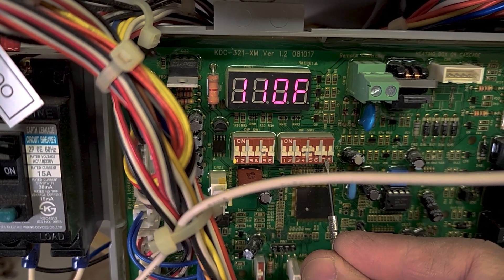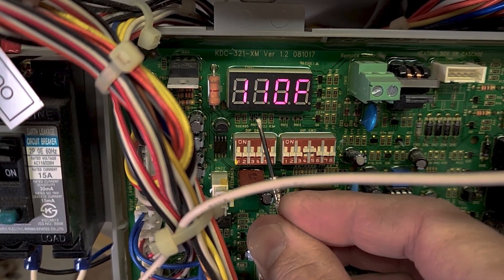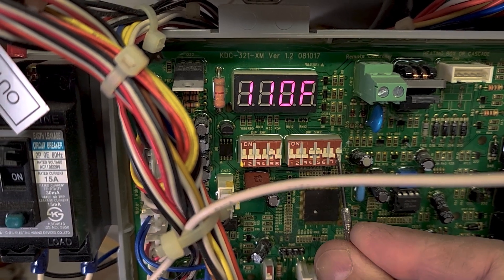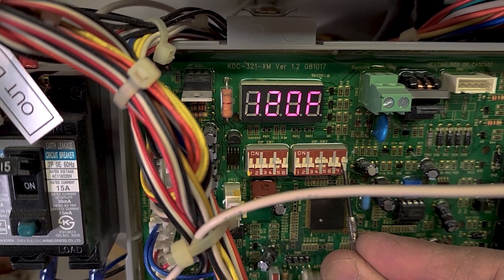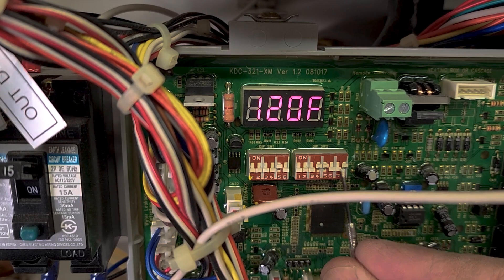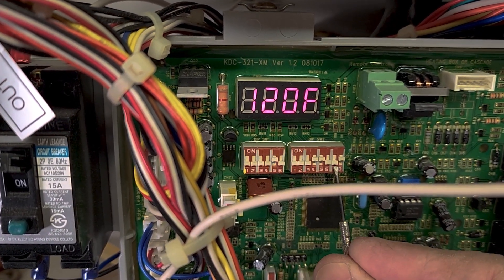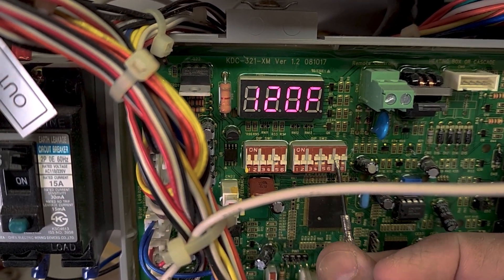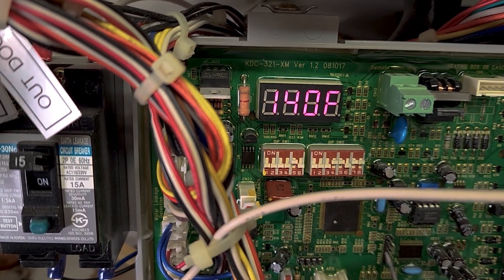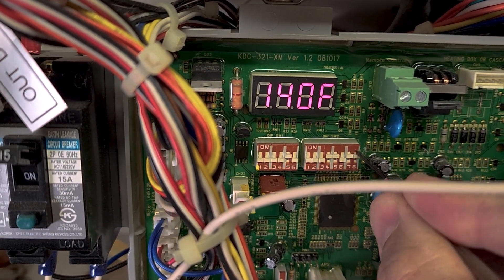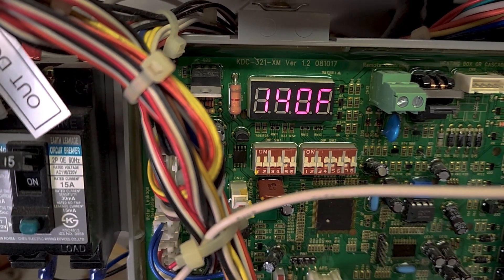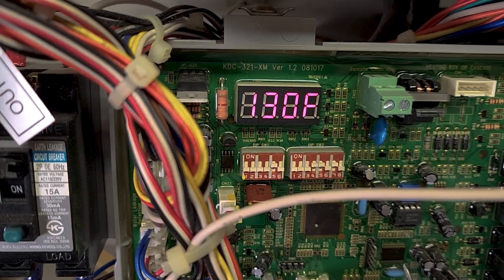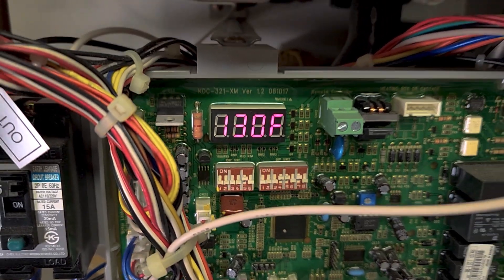So with both seven and eight being down, it will be 110 degrees. If you flip eight up, it'll move to 120. You can see that on the digital readout now. If you move this one up, it'll go up to 140. And if you move eight down, that'll go to 130 midway. So I just moved mine up from 120 to 130, but that's how you do it.